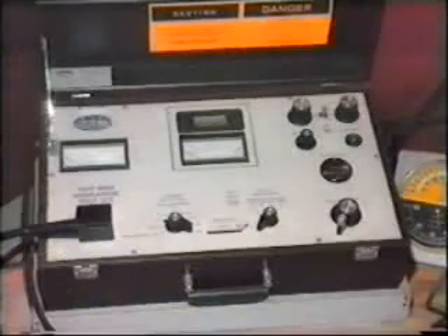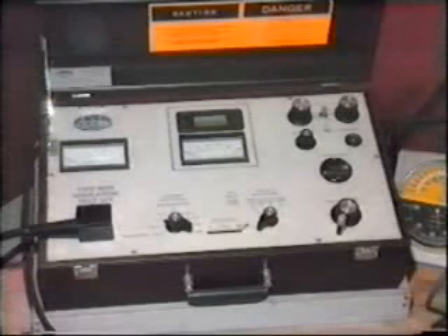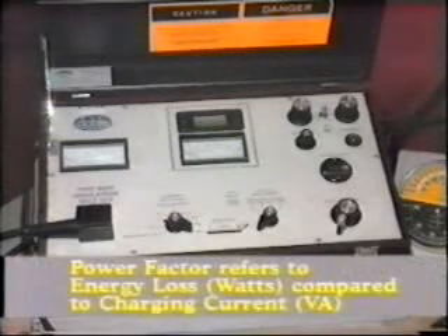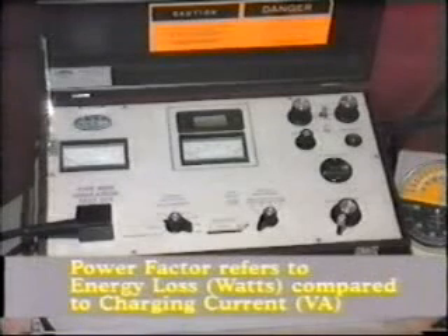Another very useful measurement which is used to check the deterioration of insulation material is the insulation power factor test. This special test equipment measures the AC dielectric loss through the insulation. The power factor actually refers to the energy loss in watts compared to the charging current, VA. For further information on this equipment, you will have to study the manufacturer's instruction manuals.